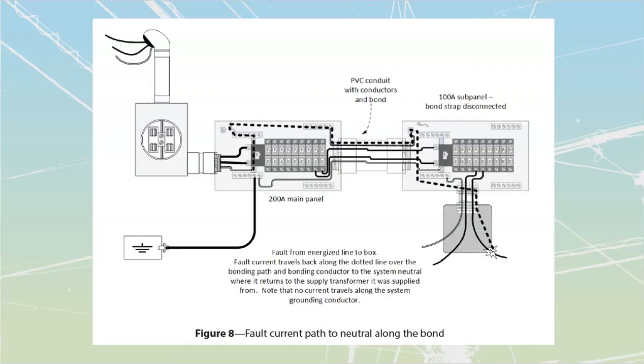Bonding is going to be the process of connecting all metallic components together so that there will be a path for current to flow. You've seen this illustration before, illustrating how we get current from our transformer. Our transformer is going to feed down through lines, into the bus bar over here. It is then going to feed into my panel. From my panel, it is then going to feed through into my sub-panel. From my sub-panel, we are then going to carry that current down my conductor. And right over there, we see where that conductor has made contact with the side of the box.